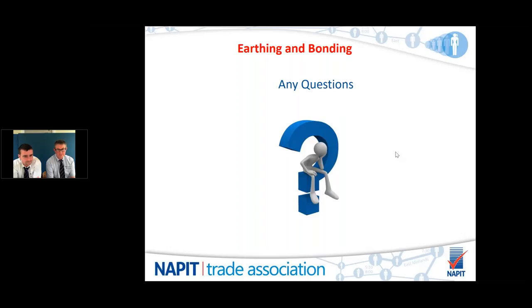Great. So we've got one from Dylan here. What is the name and minimum size of the conductor between a flush metal back box earthed via a CPC and metal light switch? CPC is 1.0. It'll just be a flying lead. Yeah, it's an earthing conductor. It's a CPC. It's a continuation of a CPC. That's all.